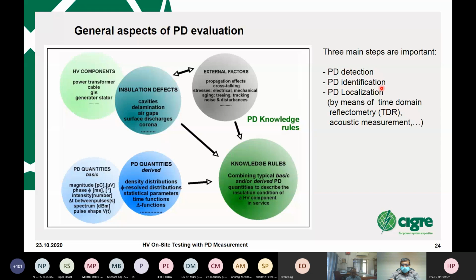That means electrically with a coupling capacitor, the UHF technology, or the acoustic method. Then the PD identification. Identification means, is it from a corona shield? Is it a free moving particle? Or is it inside a transformer on the high low voltage part? Or is it really PD from a joint? And if it's polyethylene, then normally it's really dangerous.